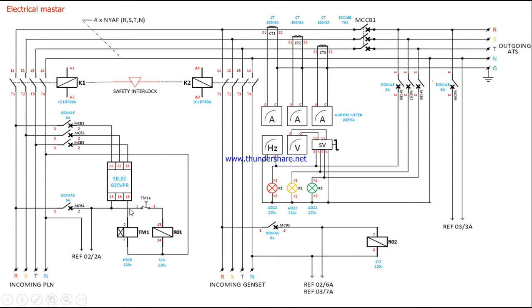From the phase failure relay, the supply is extended through the timer NO contact and connected to relay R01. Whenever the main supply is available, terminal 18 is closed and connected to timer 1, so the timer picks up. After its delay, the timer NO contact closes and supply is connected to R01, activating relay R01. The A2 terminal of timer 1 and R01 are connected to neutral, and this supply goes to the control supply of contactor K1.